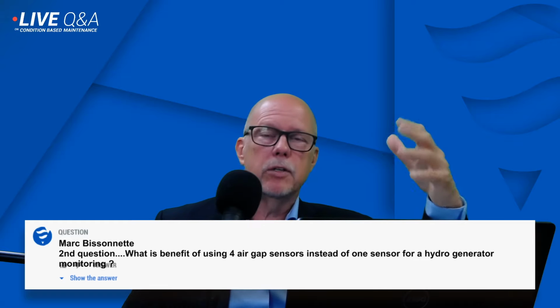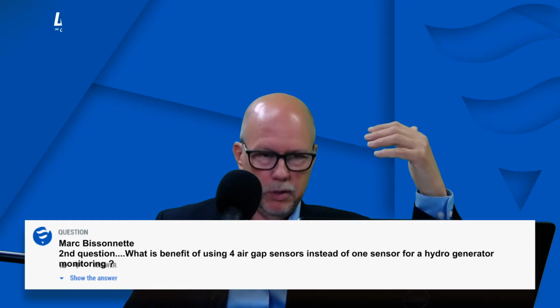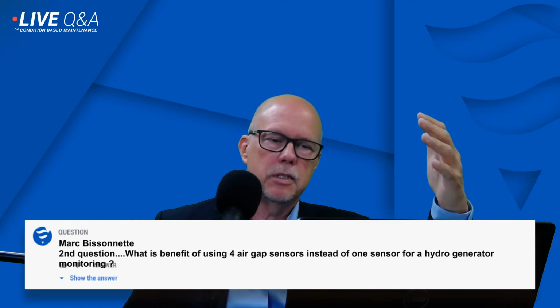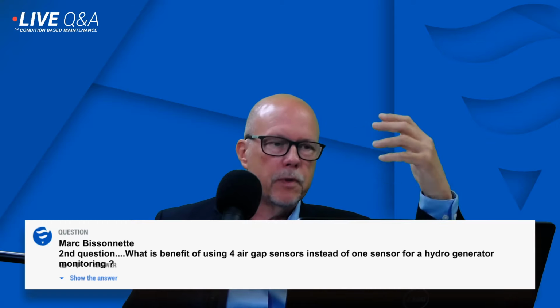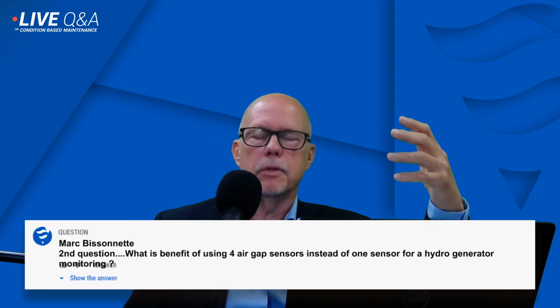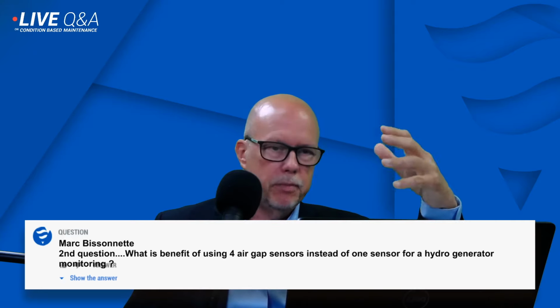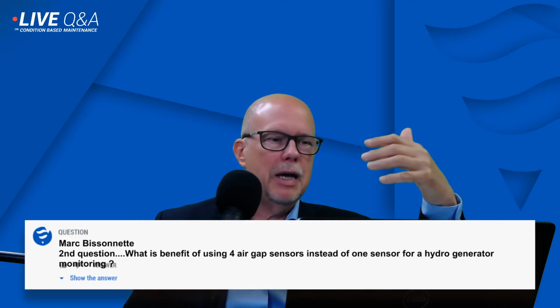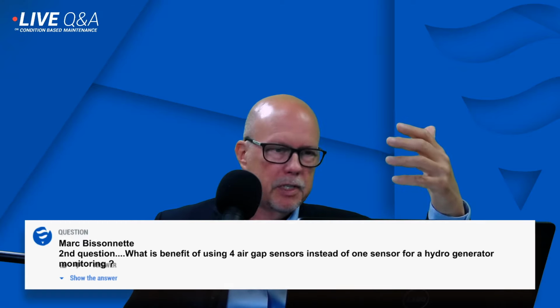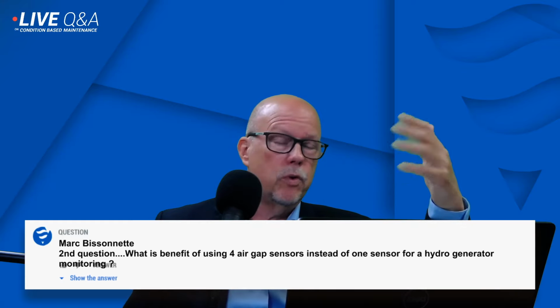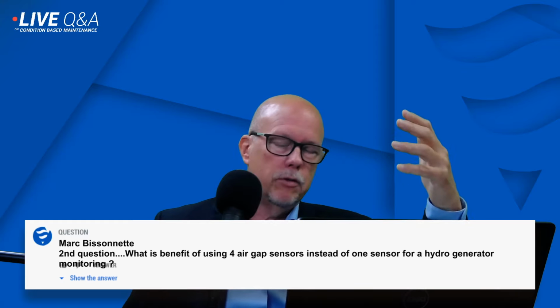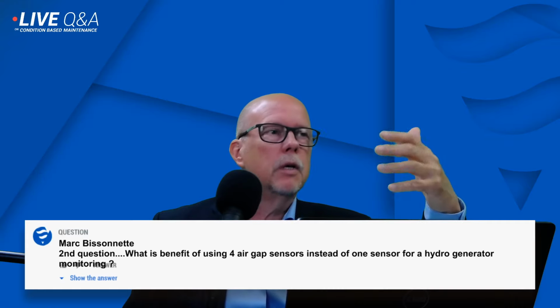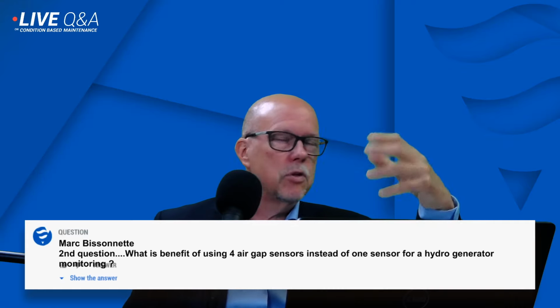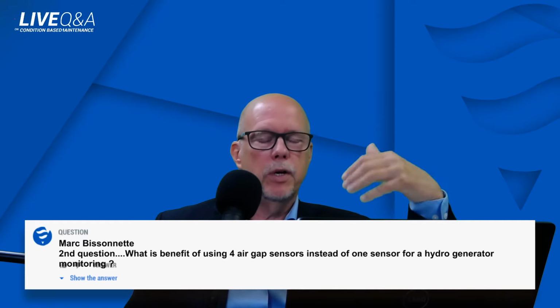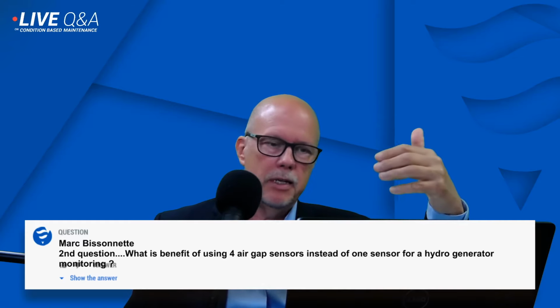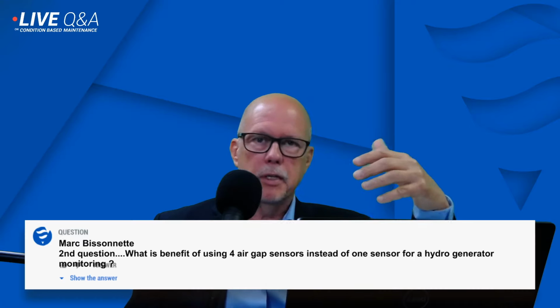So again, depending on the size, we put as many sensors as we feel is necessary to be able to come up with a good assessment of not only the stator shape, but its performance as it's exposed to a tremendous amount of heat. There's quite a few stators that we've seen that look fine when they're cold, but when you heat them up, they have sole plate issues, they have core to frame looseness issues, and when you apply heat for an extended period of time, these anomalies show up.